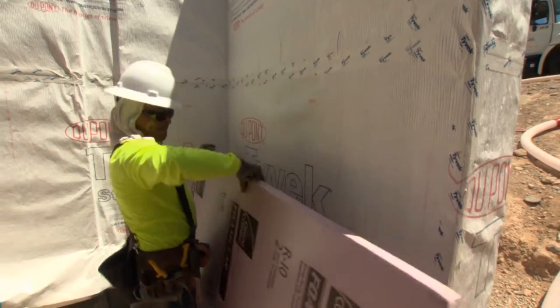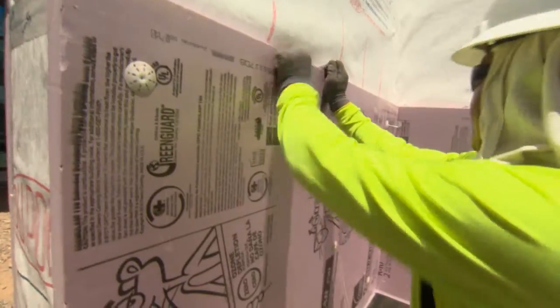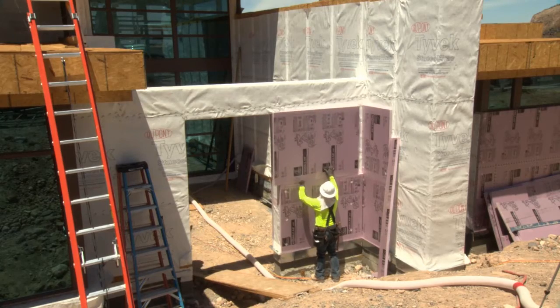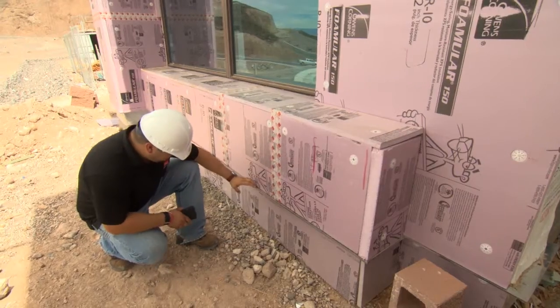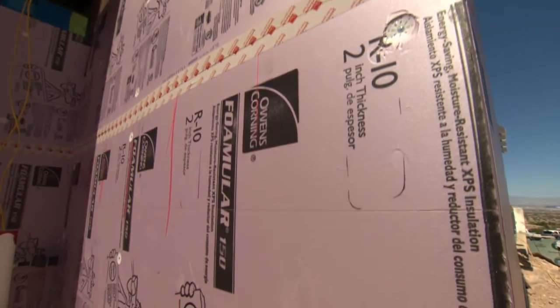By doing that, you're adding a layer of insulation prior to the wall cavity, which from an efficiency standpoint and from a performance standpoint, significantly improves the overall R-value of the home. The FOAMULAR 150 allows us to control air, moisture, and reduce the amount of thermal bridging you're going to see in a wall. Particularly in our environment where we have such intense heat, by putting that outside of the wall cavity, I think there's a huge difference in the comfort of the home and how much heat transfers into the actual wall cavity and subsequently into the room or the home.